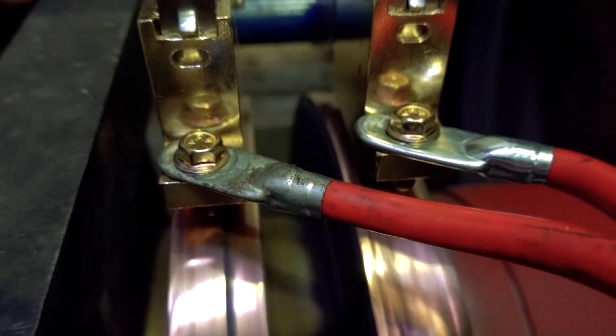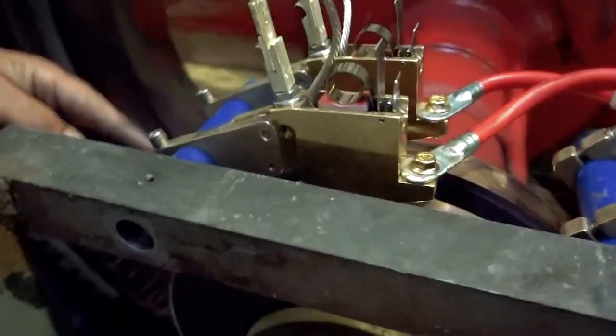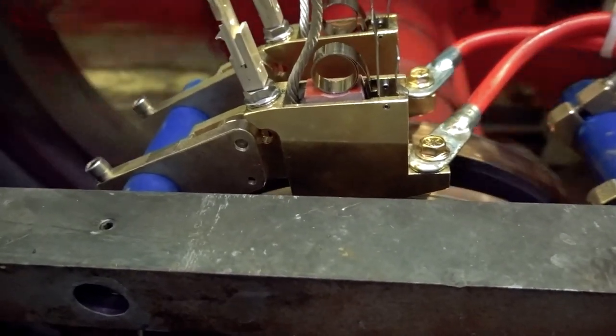get stuck. Then as wear happens, the gap between the slip rings and the brush gets bigger and bigger and eventually creates like a laser beam that scars the slip rings.